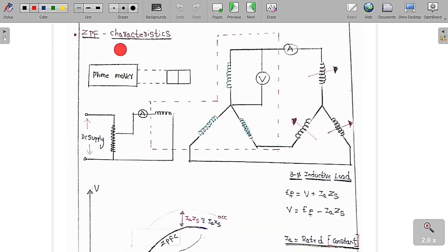Now we will understand one more important concept, the zero power factor characteristics. This is the third test. Here we draw the graph between terminal voltage and field current, with the power factor of the load constant, the armature current constant at rated value, and the speed of the rotor constant. These are the conditions.